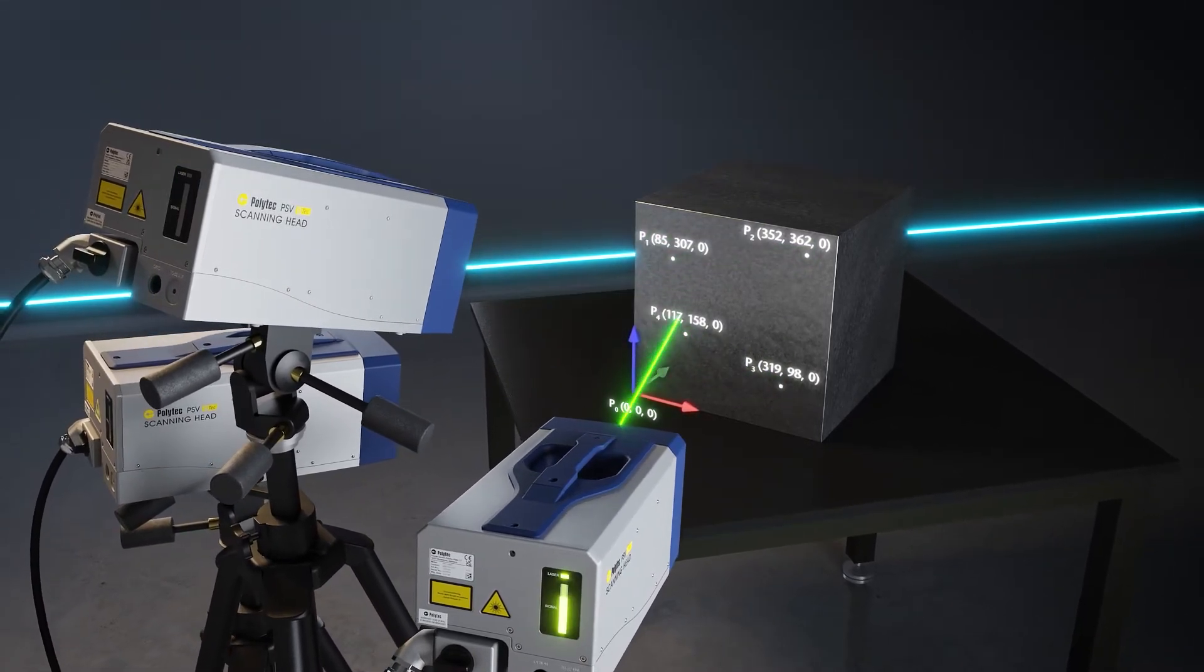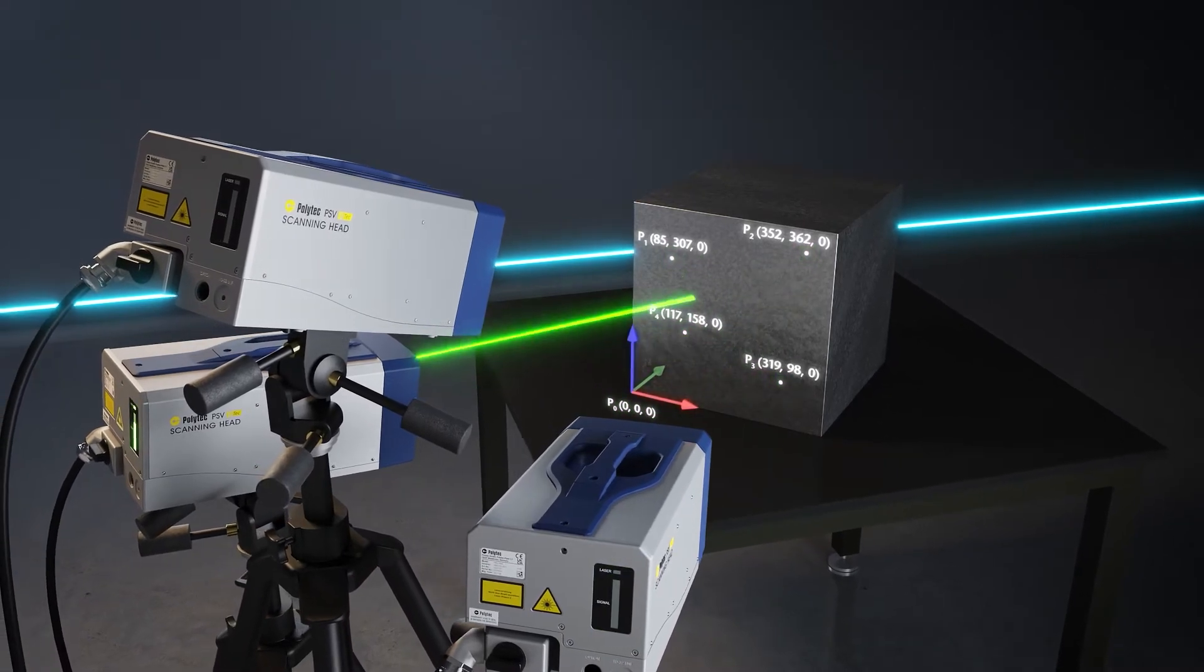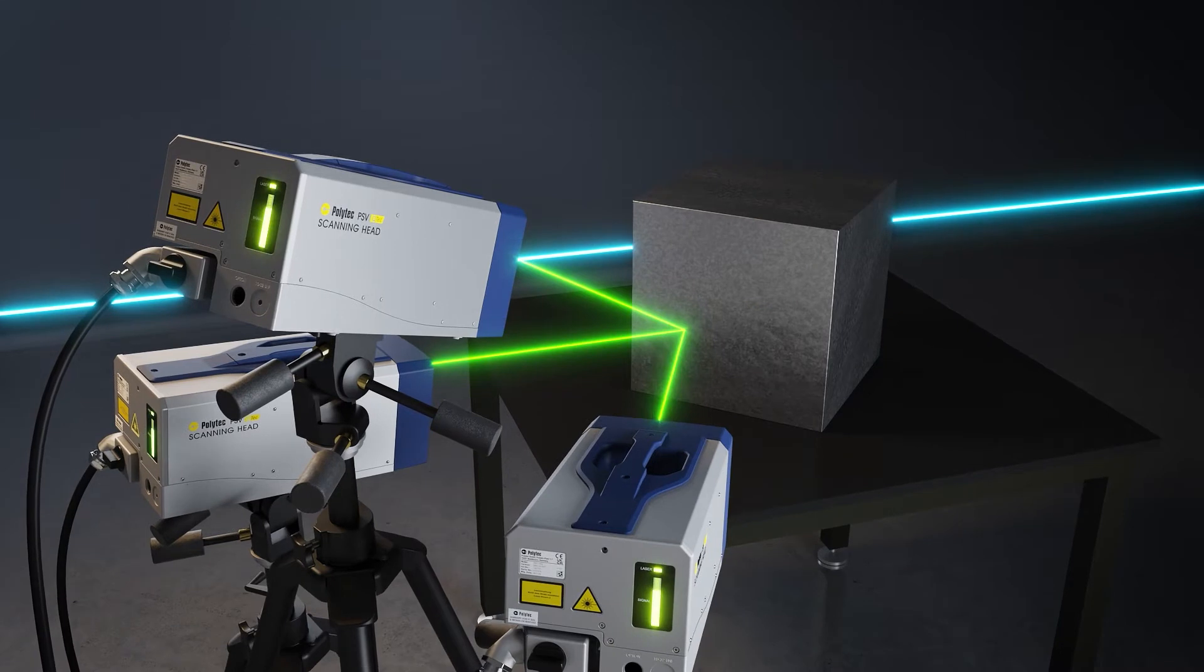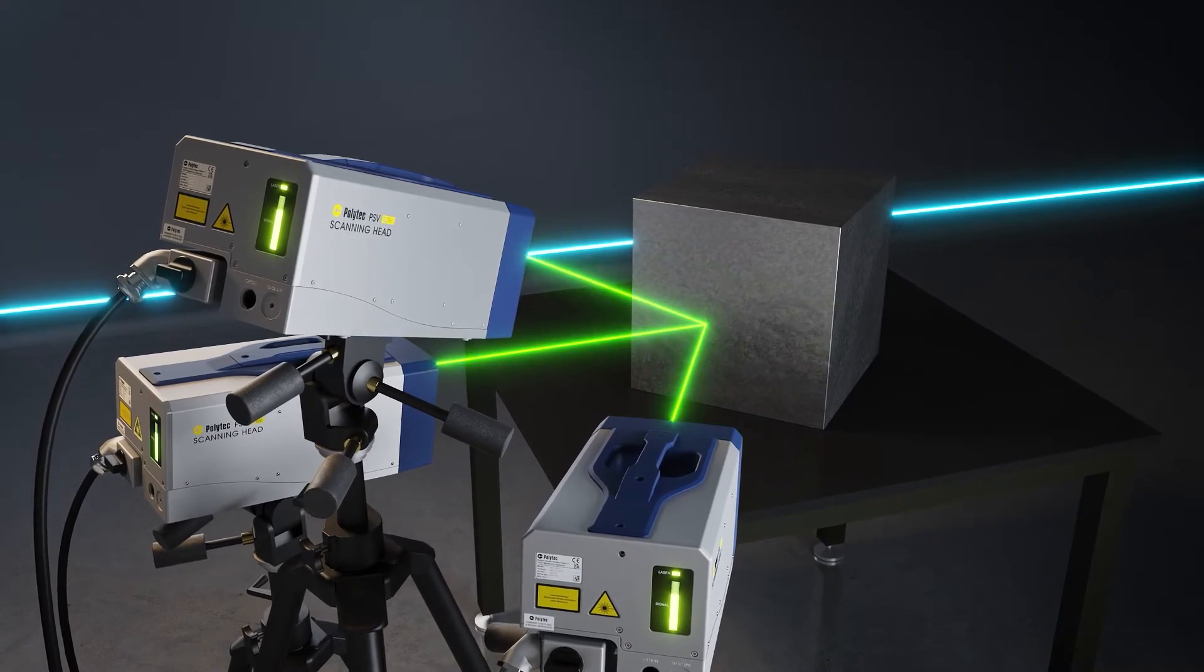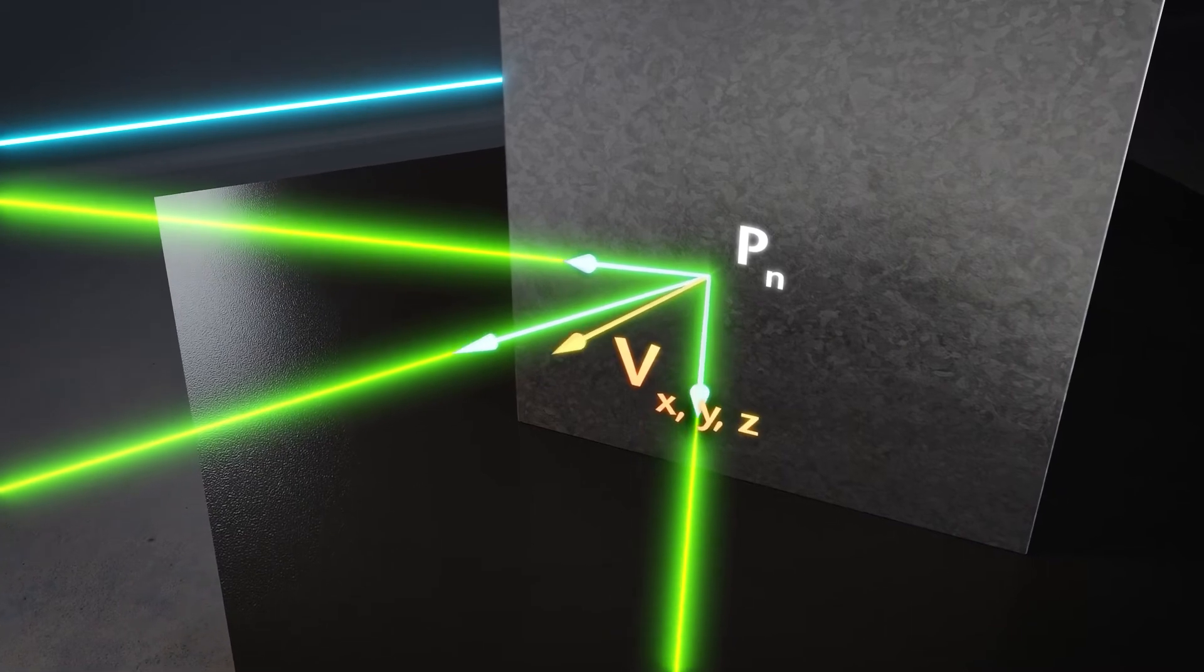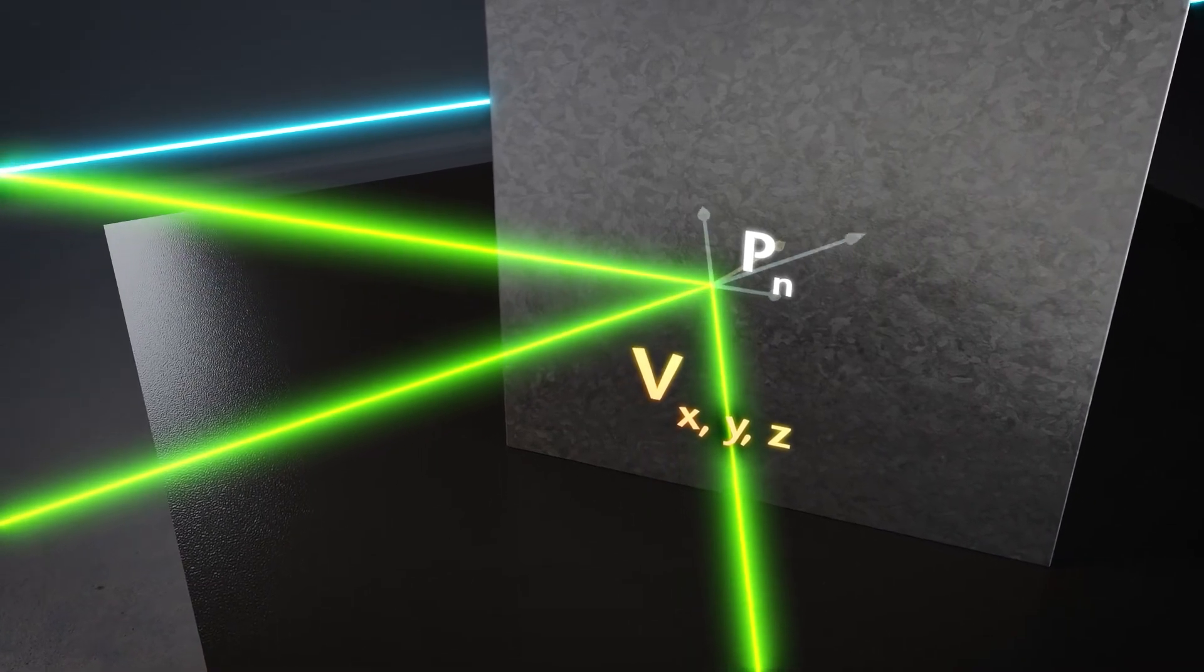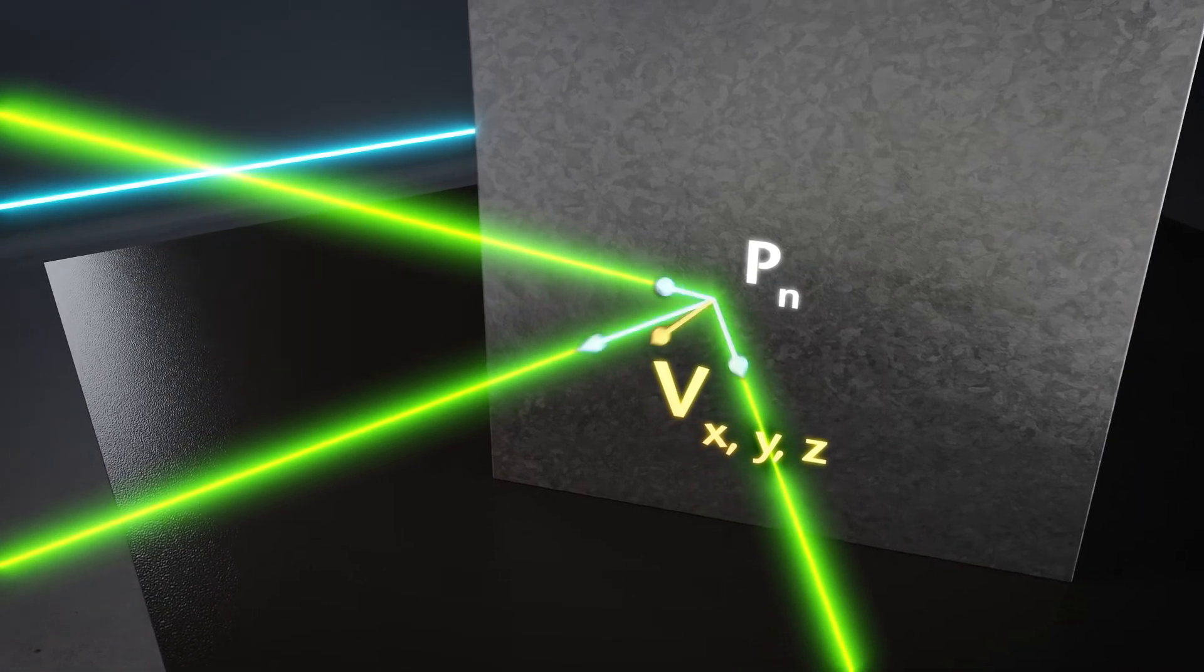Targeting at least four points from each scanning head position provides enough information for the transformation. For each point of the object, the lasers now intersect. This transforms the arbitrary vectors of the three lasers into a precise Cartesian 3D vibration vector output.